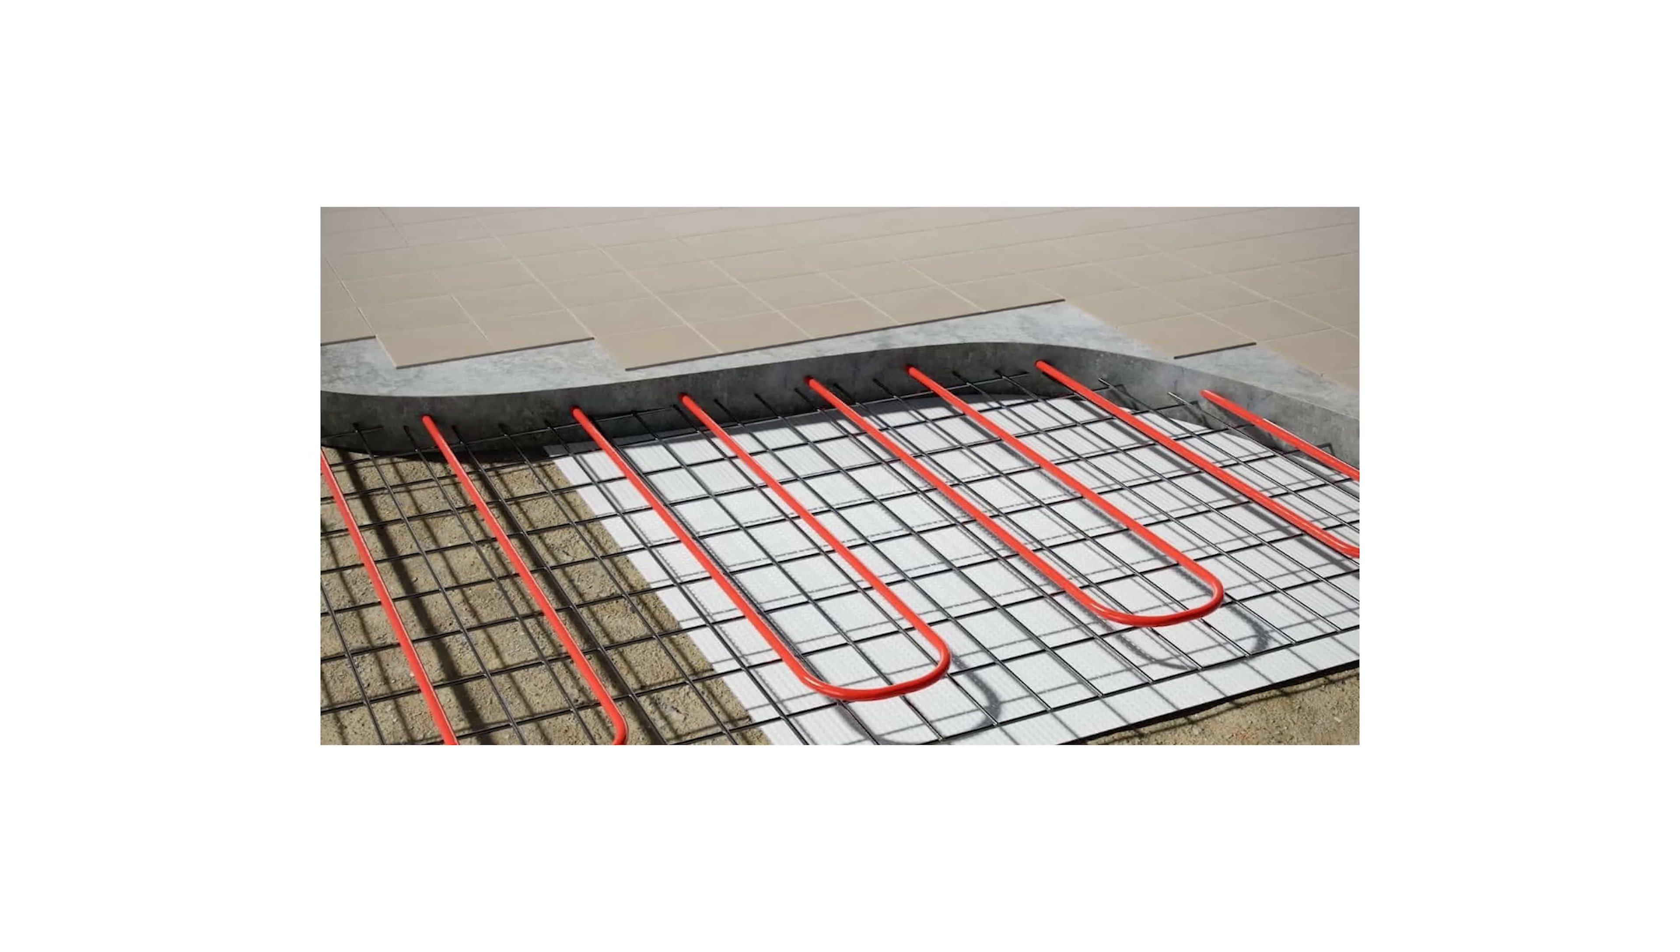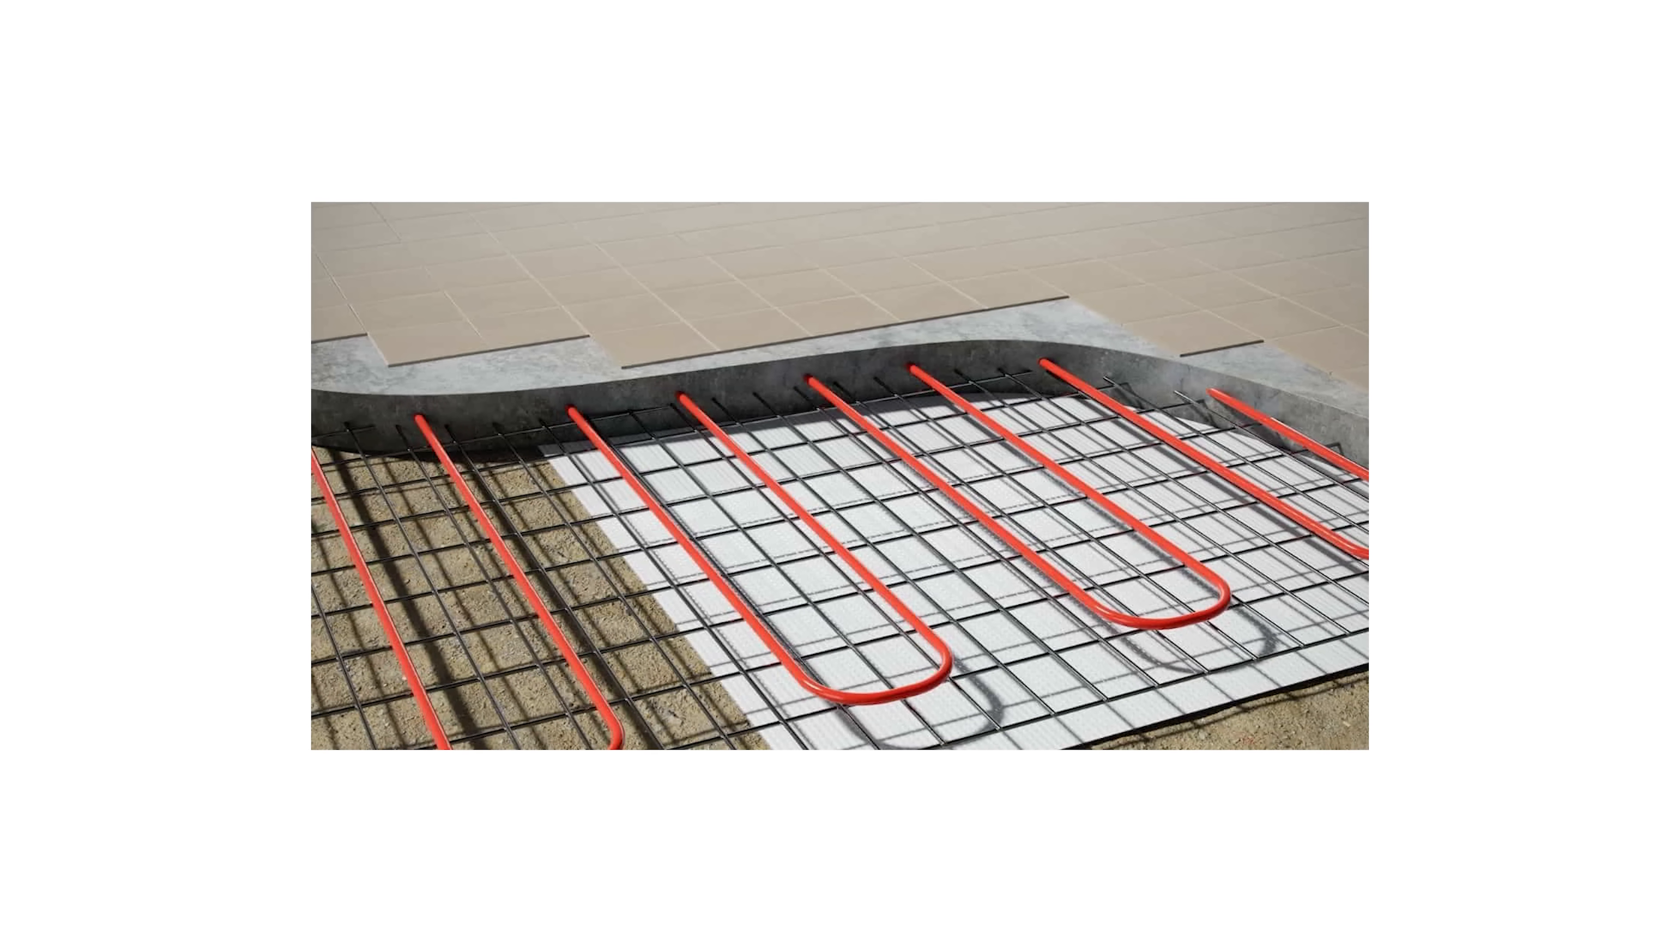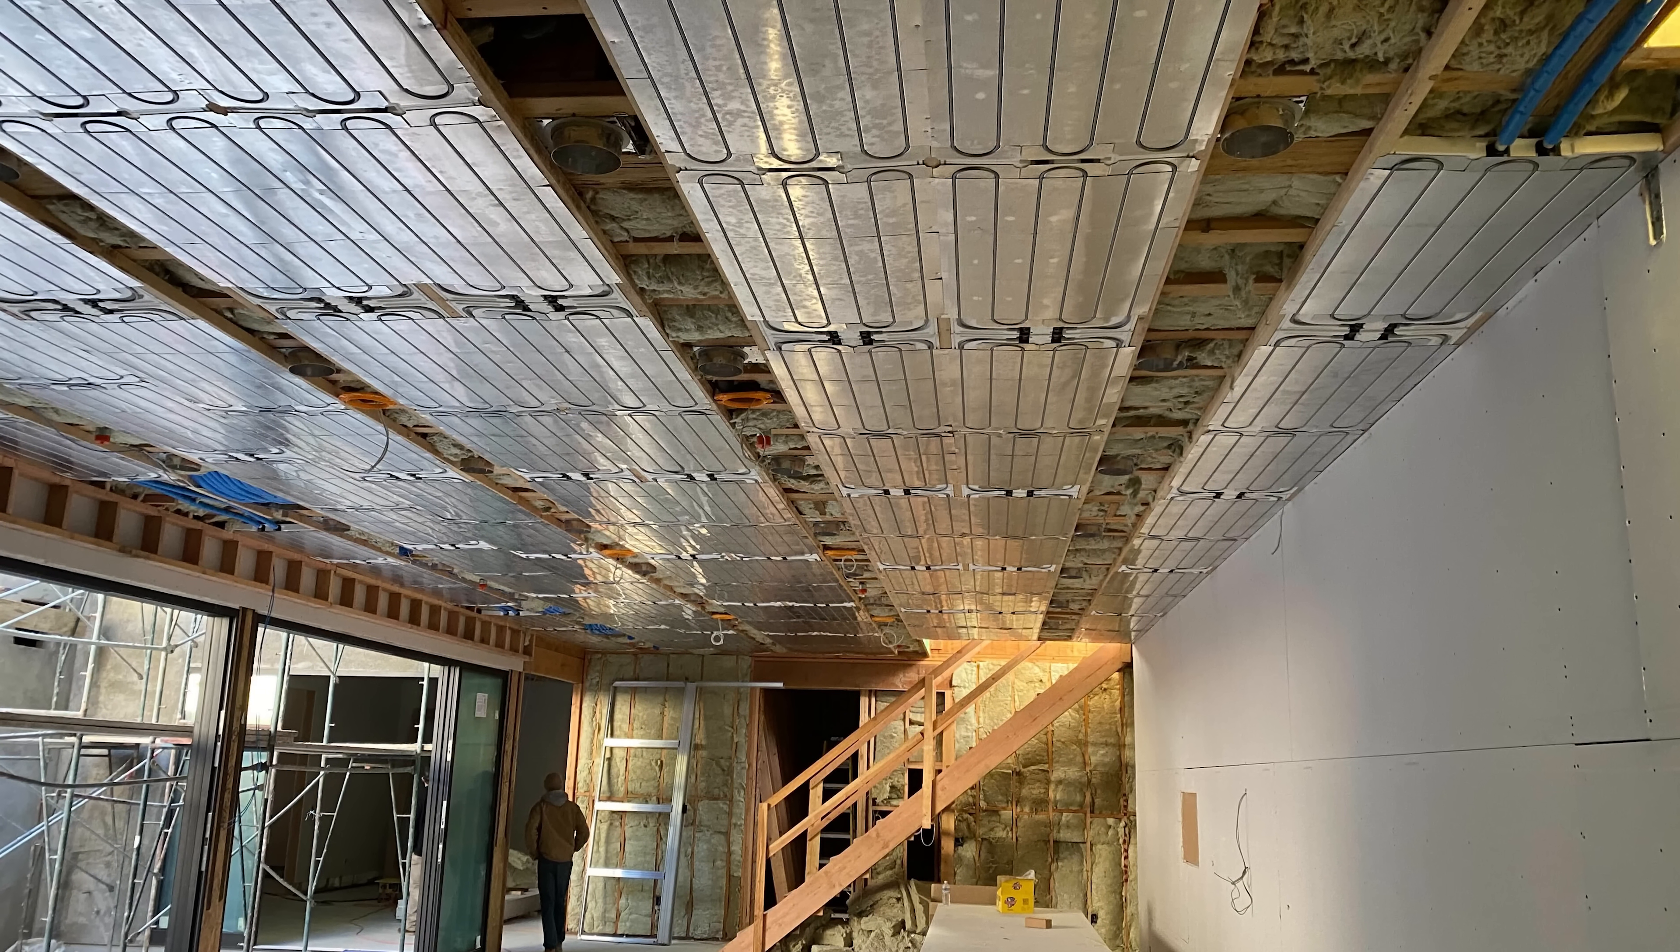We did experiments in the floor to provide radiant cooling via the floor. But we found those systems are really high in mass, so they don't respond very quickly, which is critical when it comes to battling the dew point and condensation in a radiant cooling system. So we moved the technology to the ceiling.